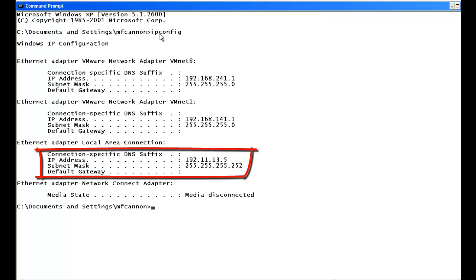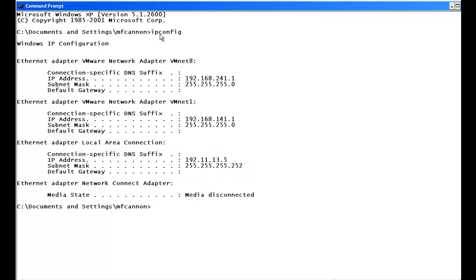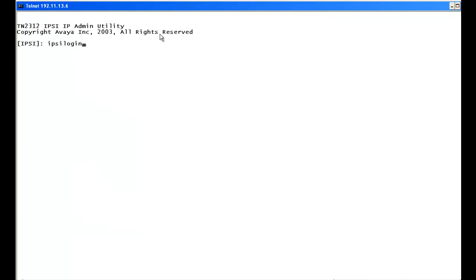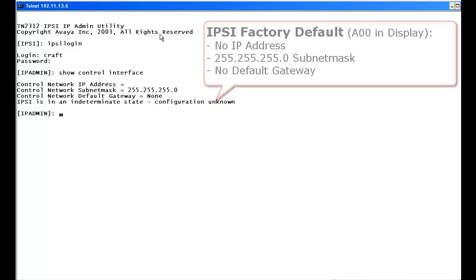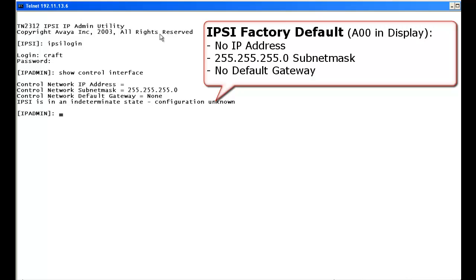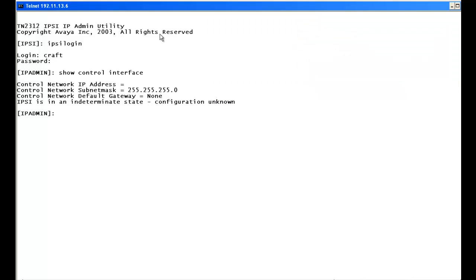The laptop is set up at 192.11.13.5 with the 30-bit mask, directly connected to the services port of the IPSI. We type telnet 192.11.13.6, enter the IPSI login with username craft and the password. To see how the IPSI board is initially set up, we type show control interface. The board shows no IP address, a 24-bit mask, and no gateway — that's the factory default A00 on the display.